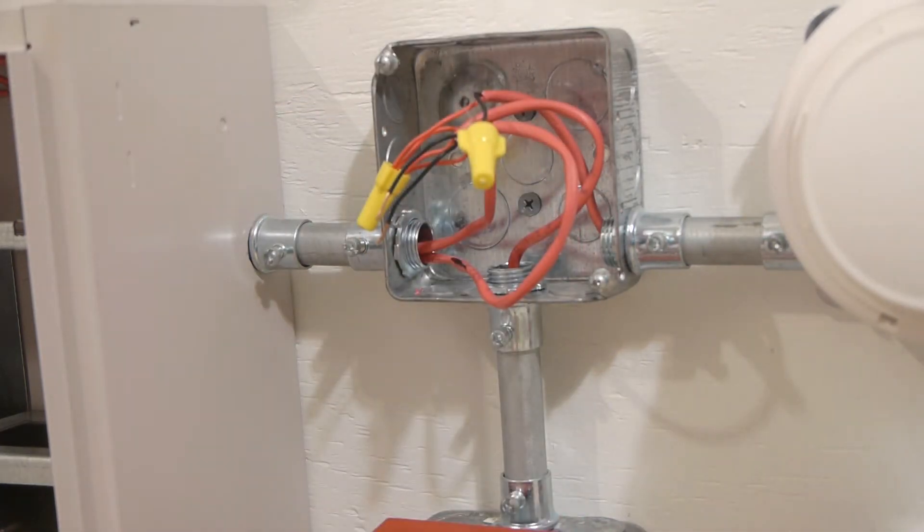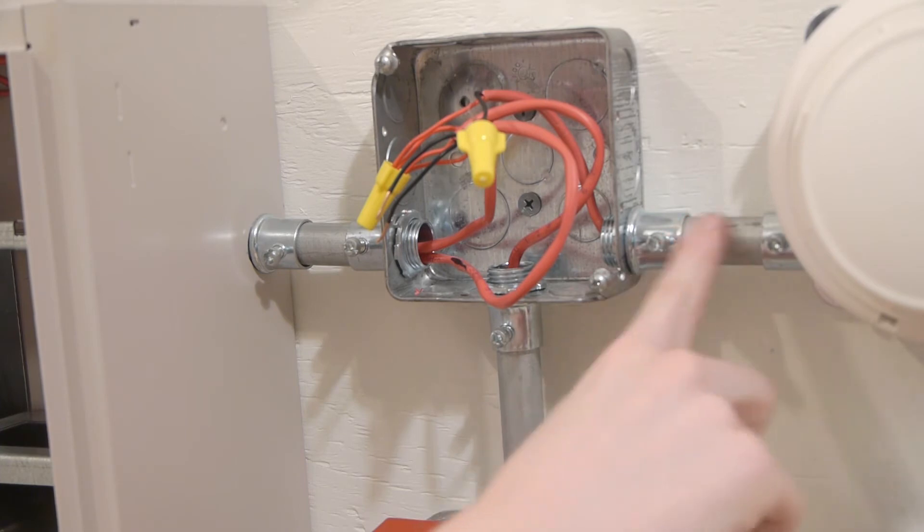There's going to be some troubles coming up because of the devices we just took off. If I scroll through the troubles, I can see the negative ground fault just came back. So that means that it is on this branch of the SLC right here.